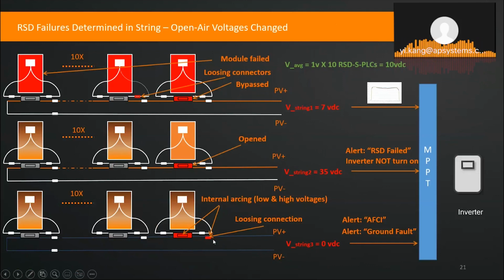Or you have a loose connection during the installation. This happens very often: a loose connection on the output or the negative coming back. They didn't get the right connector, and they have a mismatch issue and lose the contact inside the connector. You will see the string with 0 volts. When you have that kind of information, you should immediately know there is an open circuit somewhere, and you can just look for that point, the grounding point, where exactly it happened.